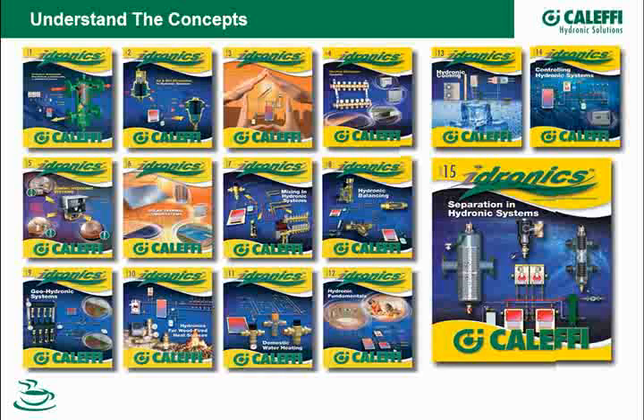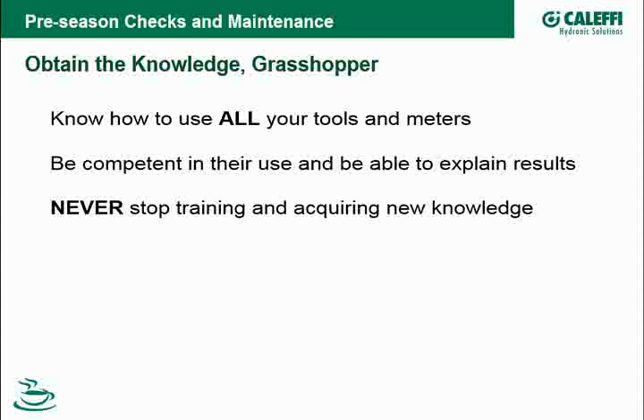You get to the job and make no assumptions, I guess. Confirm that the equipment has been sized properly. If you weren't the installer, if you're following somebody else or another service contractor who's worked on something before, just look over what they've done and just make sure everything's right. And I would say probably the biggest thing you'll see out there if you're doing a lot of troubleshooting or service work is equipment that's been oversized, grossly oversized in some cases.